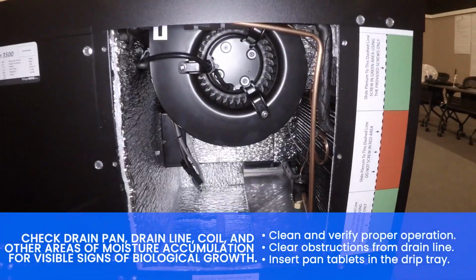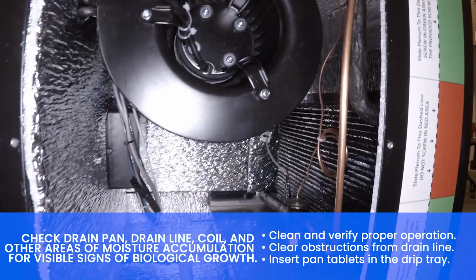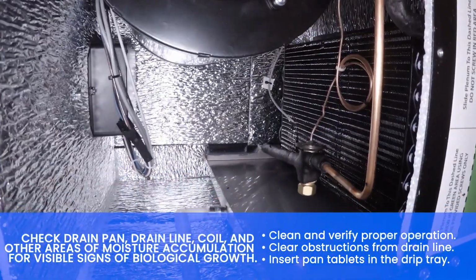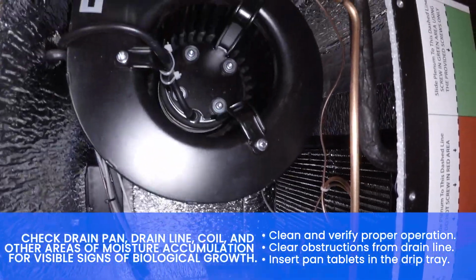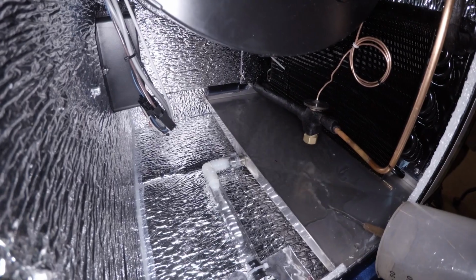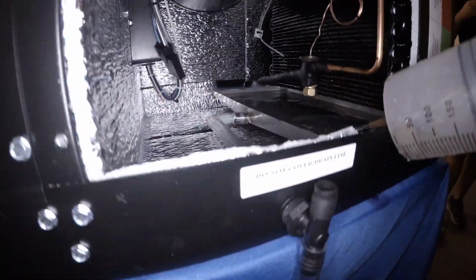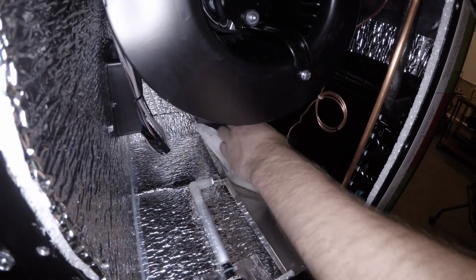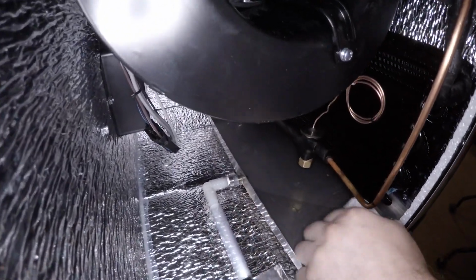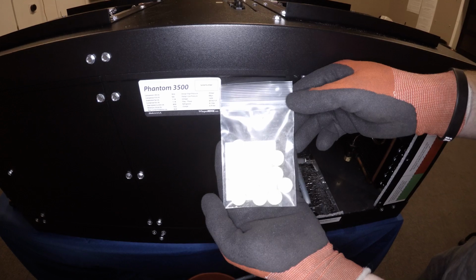Check the drain pan, drain line, coil, and other areas of moisture accumulation for visible signs of biological growth. Perform condensate drain tests to verify proper drainage, then remove excess water from the internal drain pan after the test has been performed.